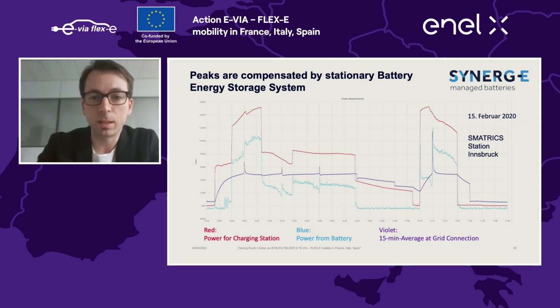Here's another screenshot, data from multiple charging events. An additional data line is provided in violet, the 15-minute average at the grid connection point, which determines the grid fee paid by the charging operator to the distribution system operator. This violet line is more or less constant at roughly 50 kilowatts, which was the peak shaving target for this system.